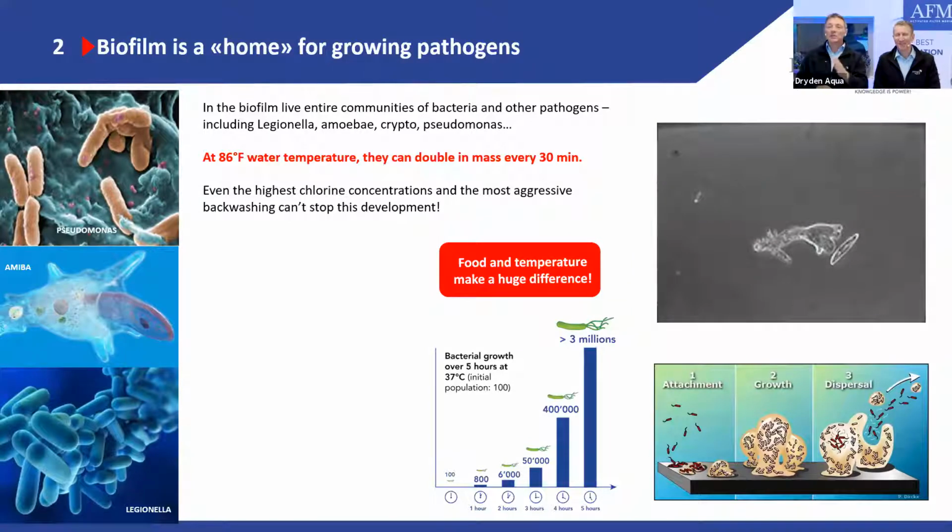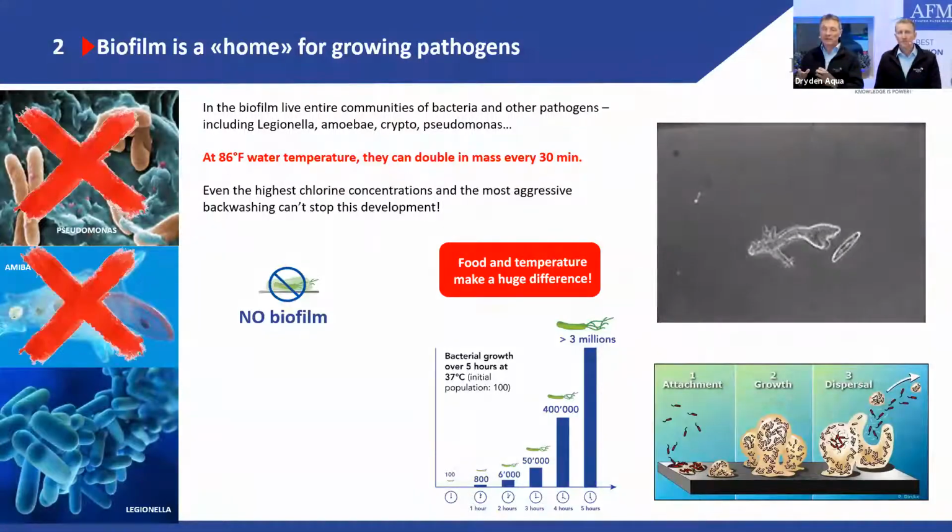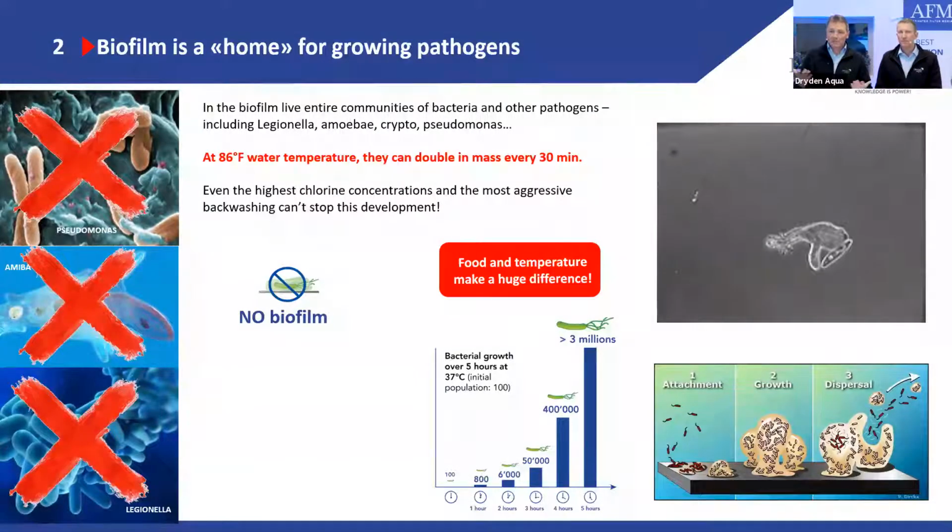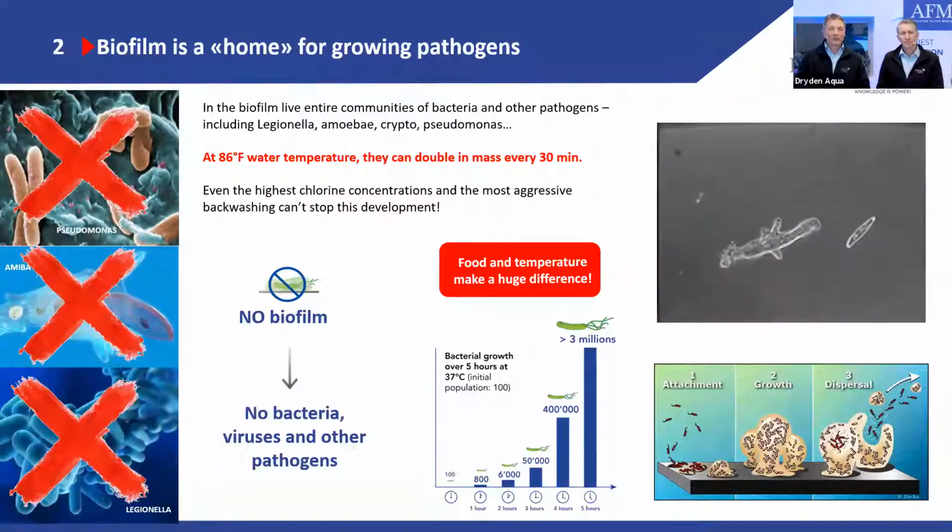No, you're good. Legionellas can live in water or in biofilm, but not amoebas. Amoebas can only live in biofilm. So if you don't have a biofilm because you have a bioresistant filter media, you don't have amoebas. If you don't have amoebas, you don't have Legionellas. I'm not a biologist. This is all what I've learned from Howard. And that makes so much sense to me, and it really corresponds. I could tell some experiences, but I will not do it for the moment, which proves that Howard is 100% right.